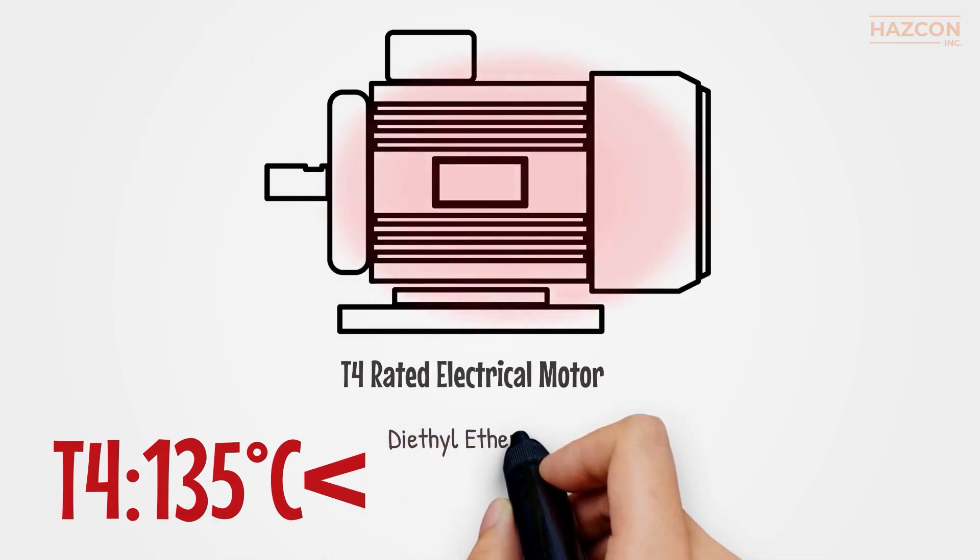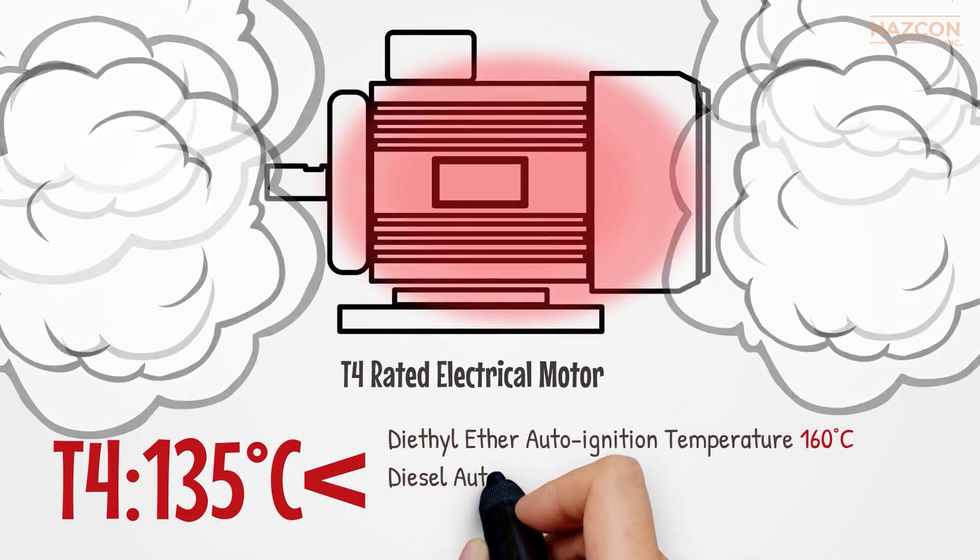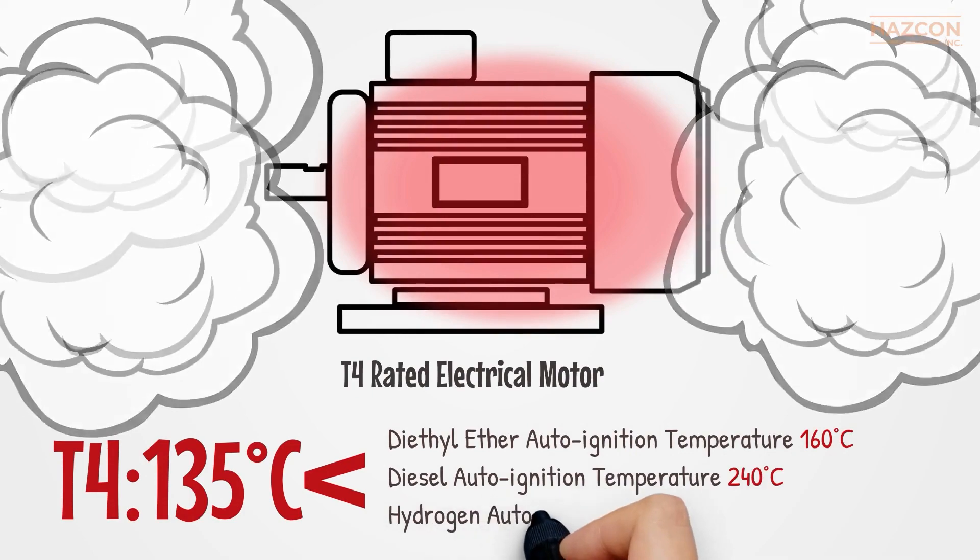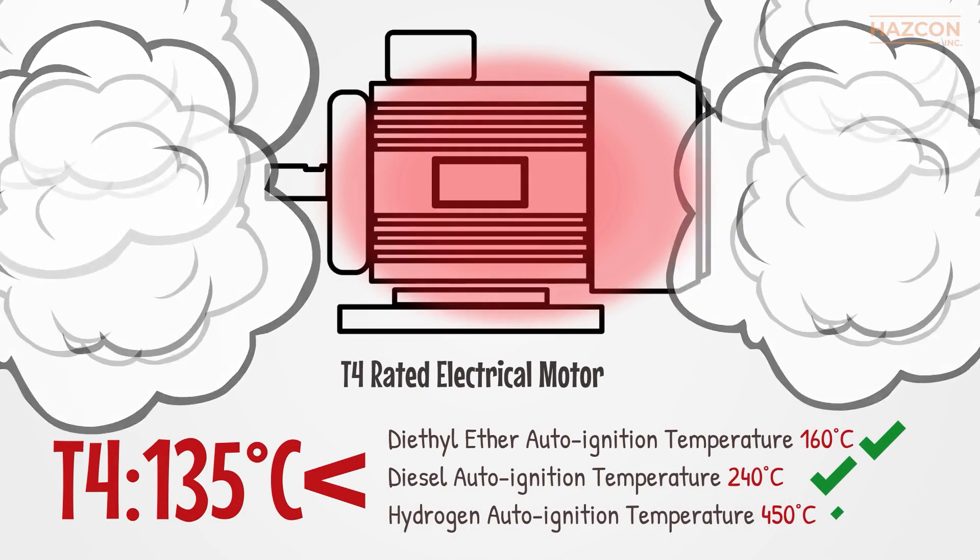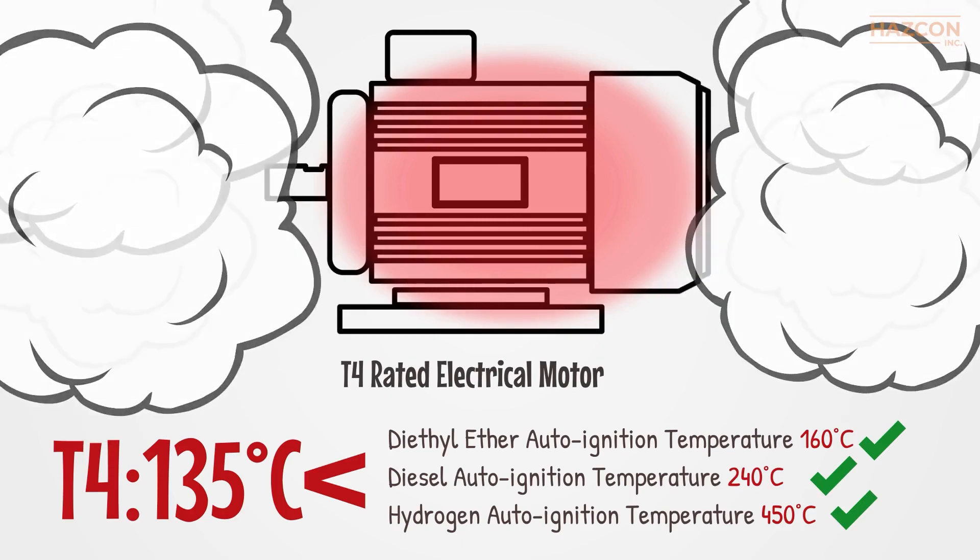Now this T4 rated electrical motor can be safely installed in an area when diethyl ether, diesel or hydrogen are present because the minimum ignition temperature of these gases is higher than maximum surface temperature rise of our T4 motor.